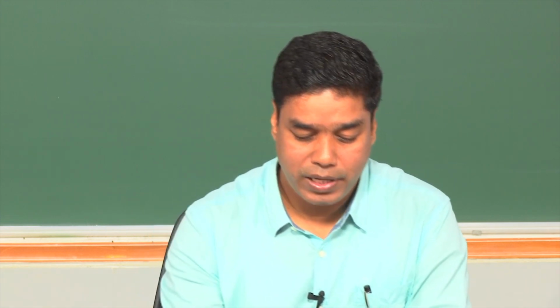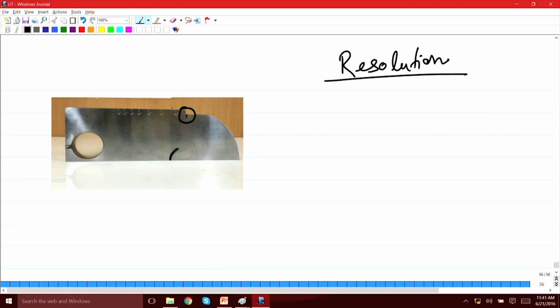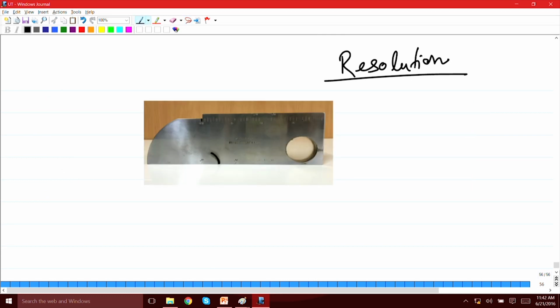With the help of this particular notch that you have over here, you would be able to find out whether the resolution for that particular probe is good or not. And this, we know, is a 2 mm wide notch. So, you place the probe over here on this surface, and then get echoes from this notch from 3 different points. First you get an echo from this, and then from the root of the notch like this, and then again from the other side of the notch.